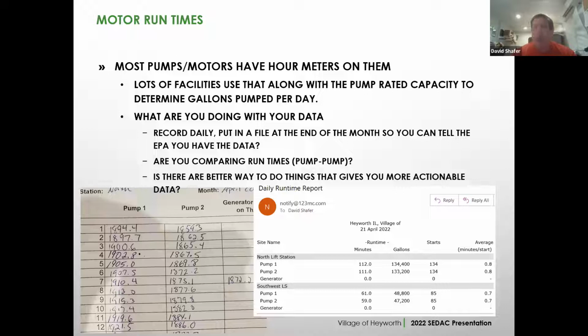On the right-hand side is a copy of part of an email I get every morning. It takes about 10 seconds to read. I get my run times in minutes, an estimate of how many gallons based on the pump run time and pump rate, how many starts each pump had, and an average run time for each start. Not a whole lot more data, but a lot more actionable. I can do a lot more with it.